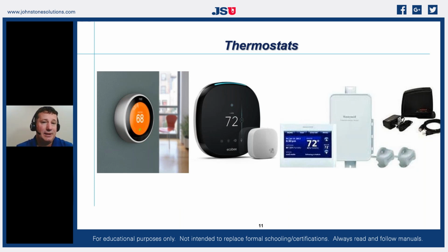And we don't really think about thermostats as being universal, but they really are. If we look at what has changed in the thermostat industry in the last 10 years, I can now take a thermostat and operate about 90% of the pieces of equipment that are in our field. So we can talk about single staging, multi-staging. We can do, in some instances now, modulating furnaces and inverters, because once we get into the Amana Comfort Bridge platform, all I need is a single stage thermostat to operate those. I can operate boilers. I can operate a variety of pieces of equipment because of the multiple terminals that I use and the ability to tell this thermostat what it's actually going to be controlling. I even have additional terminals.